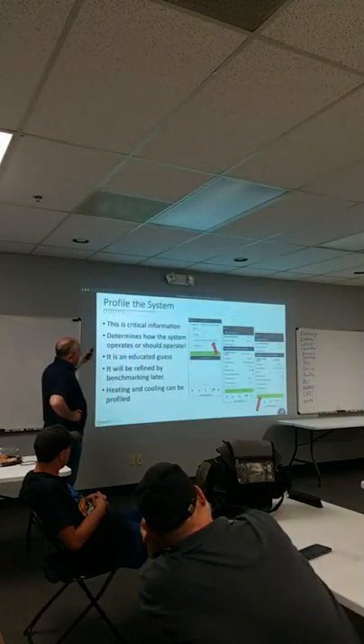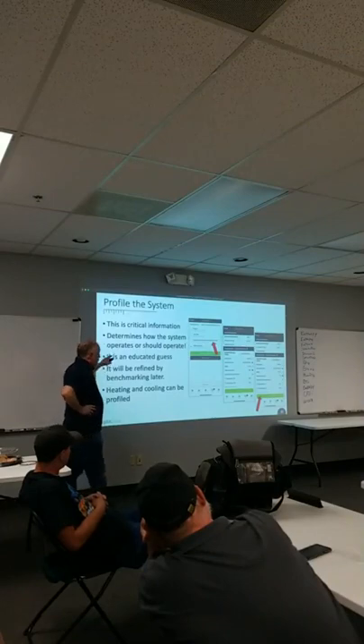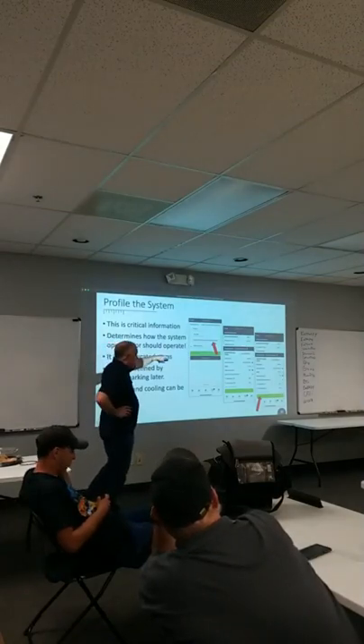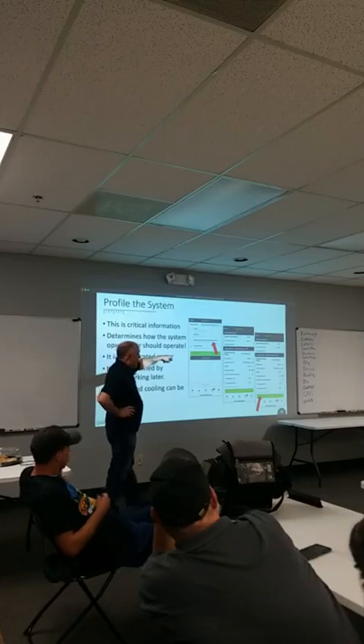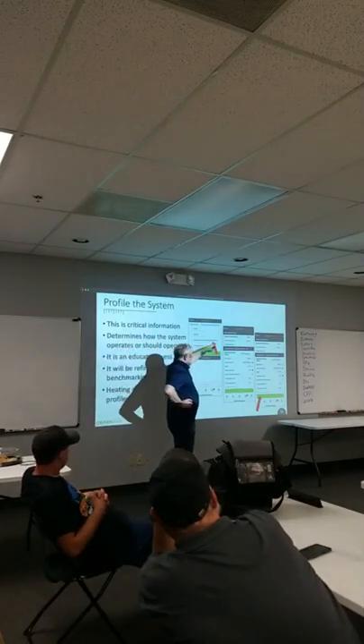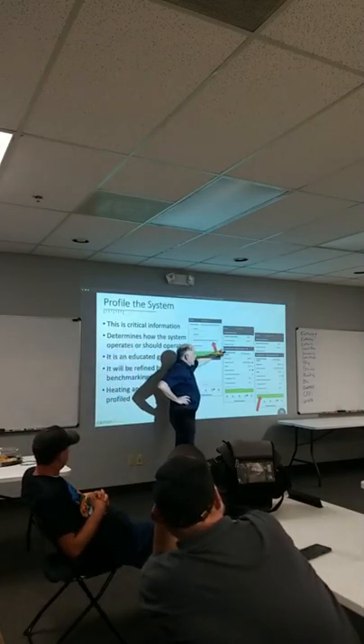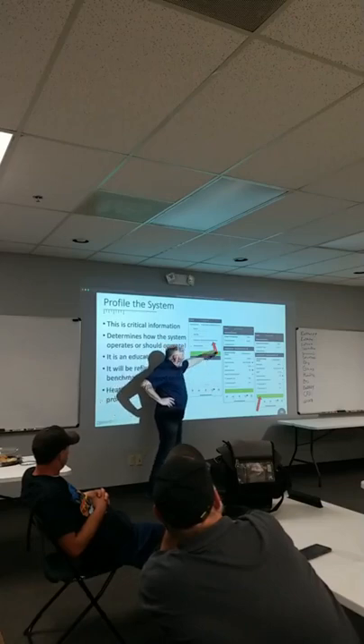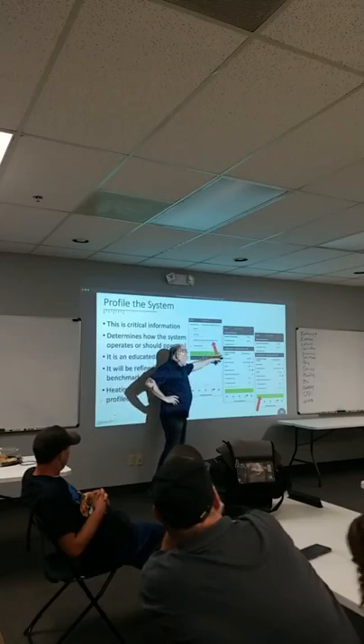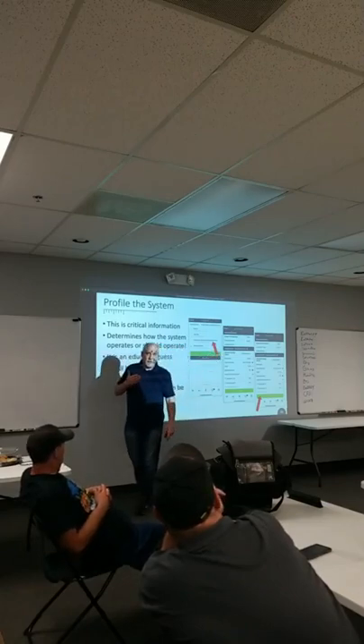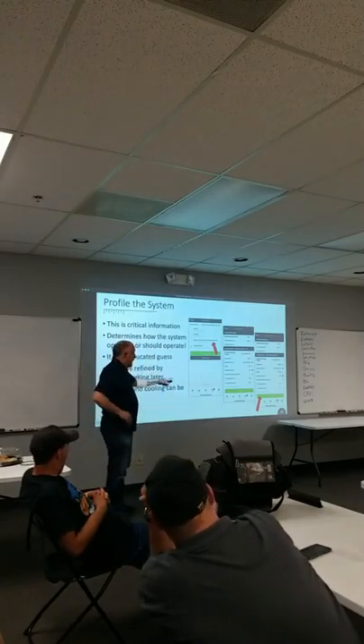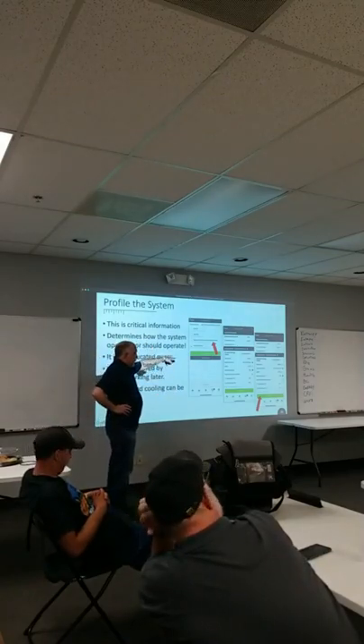Right? Profile the system. This is one of the most important steps. We're talking about after probe placement, we've got to tell it what your configuration is. Is it a split or is it a scroll? Does it have variable airflow or not? In other words, does the airflow increase or decrease with the capacity if it's multiple stage? What tonnage is it? What refrigerant is it?